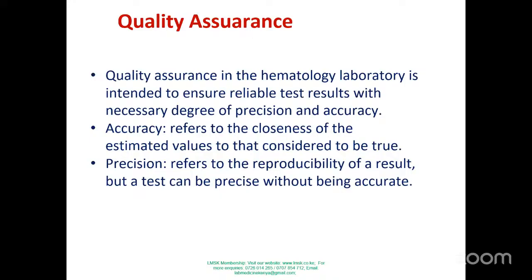So it would be sampling, it would be pipetting techniques, especially if you are not using the automated platform, and if you're using the automated platform, maybe the probes are not working well. Those are some of the things to check, and also the sample volume. Maybe you are giving it a small sample volume, or even the presence of a bubble. So that could be a random error. You have to eliminate such kinds of errors in your system.